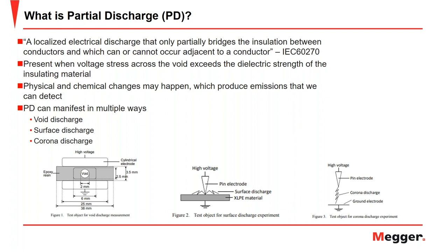And when partial discharge activity takes place, many different physical and chemical changes may happen, which produce emissions that allow us to detect the partial discharge activity. And this can come in the form of dielectric losses, electromagnetic transients, pressure waves, sound, light, heat, and even chemical reactions. Some of this partial discharge can produce ozone, and this is particularly an issue in encapsulated environments where that can get to a real corrosive atmosphere.